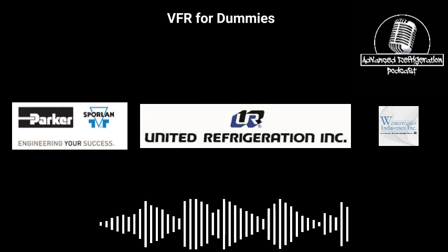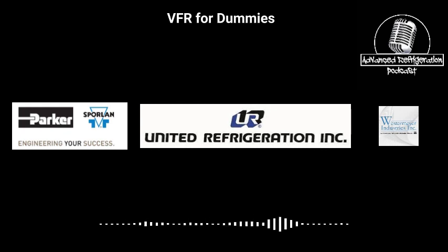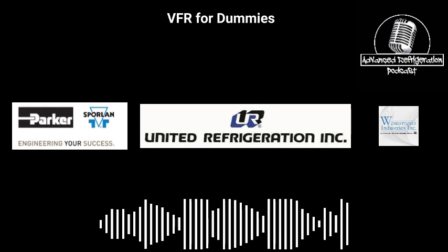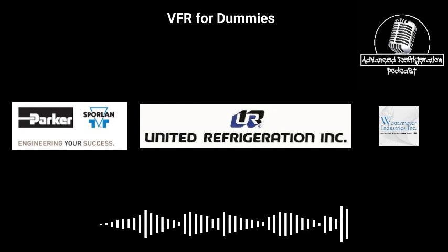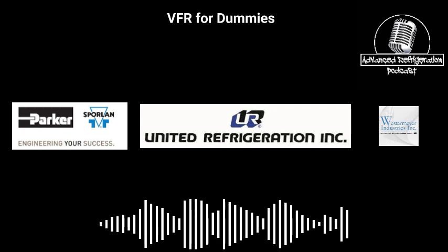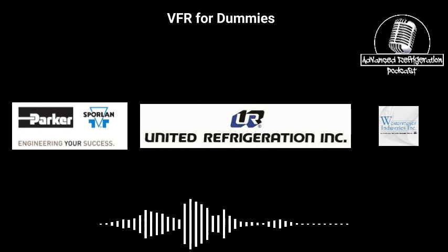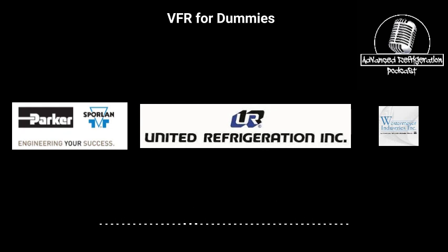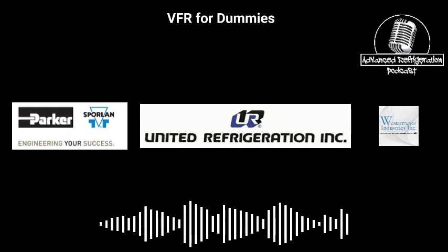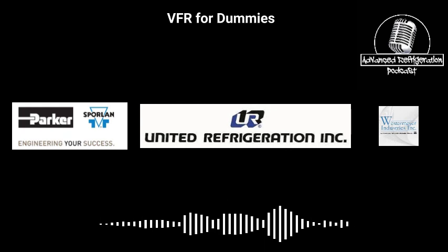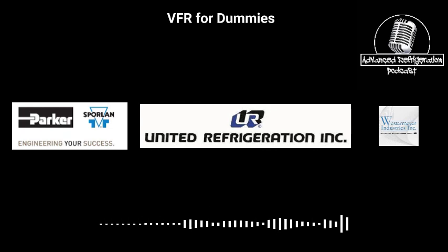So wait a minute. There's an electronic expansion valve there. There's electronics everywhere. Plenty of them. What is that one doing? These ones here? Well, I was going to say the one that's going out. I forget which line. Yeah, those ones right there. These ones are what control the coils. Okay. You can kind of see the arrows, but it doesn't really make sense. So we have sensors on each side of the coil, entering and leaving, and expansion valves that control those. Basic superheat across them.